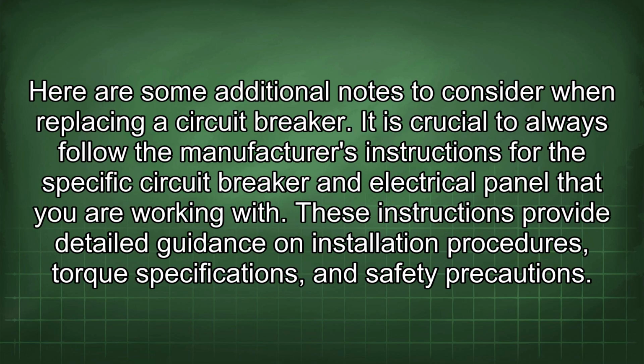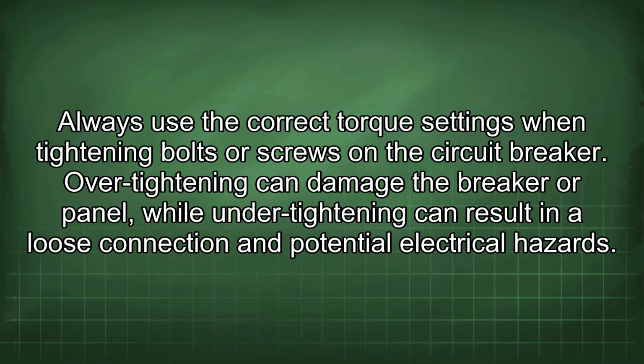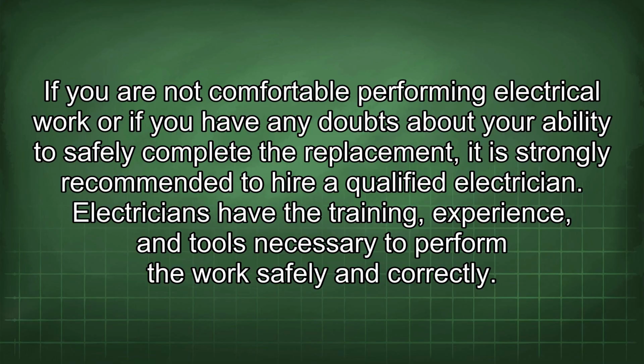Here are some additional notes to consider when replacing a circuit breaker. It is crucial to always follow the manufacturer's instructions for the specific circuit breaker and electrical panel that you are working with. These instructions provide detailed guidance on installation procedures, torque specifications, and safety precautions. Always use the correct torque settings when tightening bolts or screws in the circuit breaker. Over-tightening can damage the breaker or panel, while under-tightening can result in a loose connection and potential electrical hazards. If you are not comfortable performing electrical work, or if you have any doubts about your ability to safely complete the replacement, it is strongly recommended to hire a qualified electrician. Electricians have the training, experience, and tools necessary to perform the work safely and correctly.